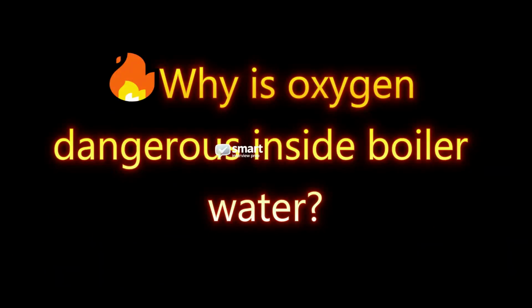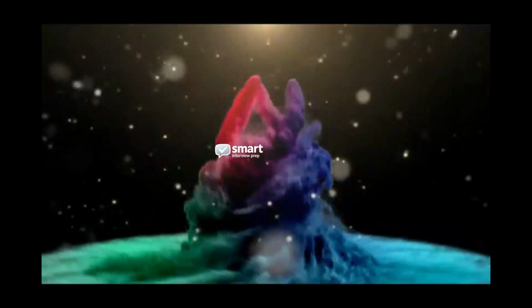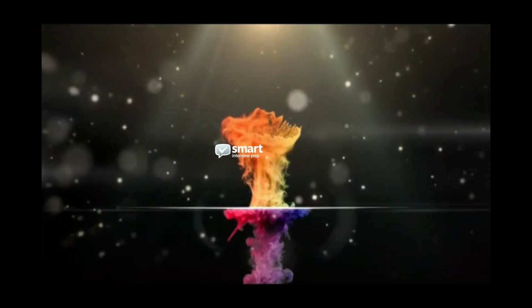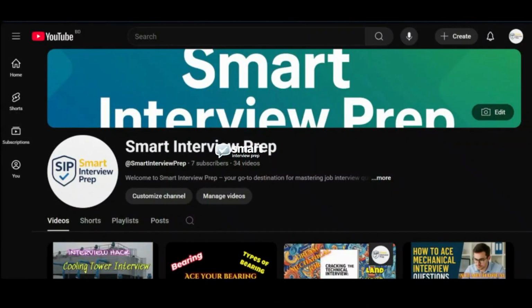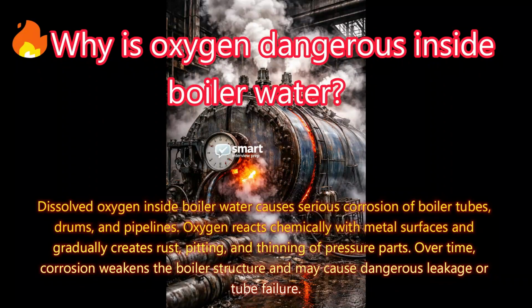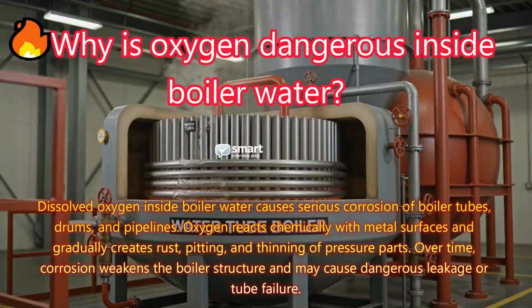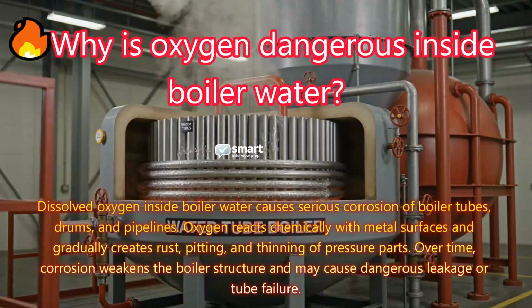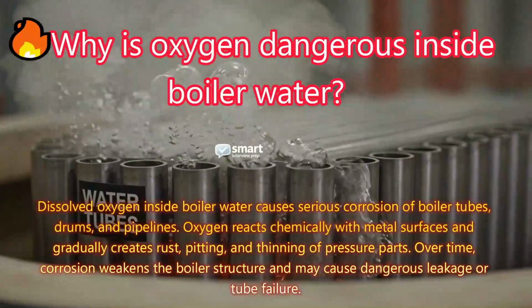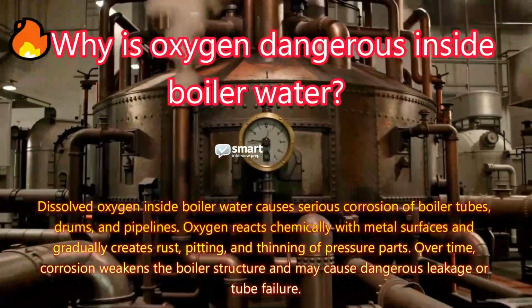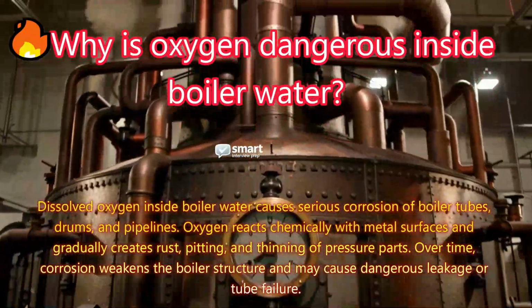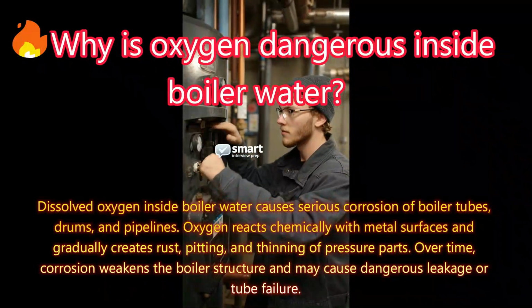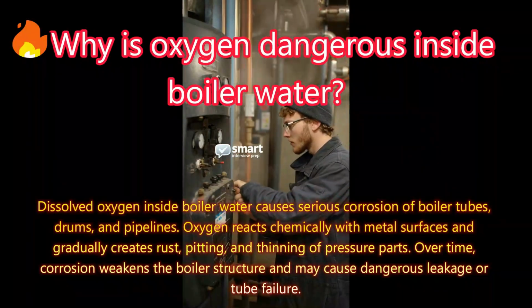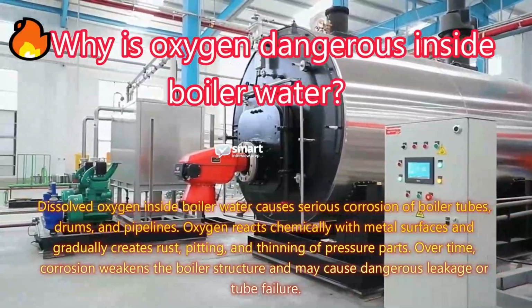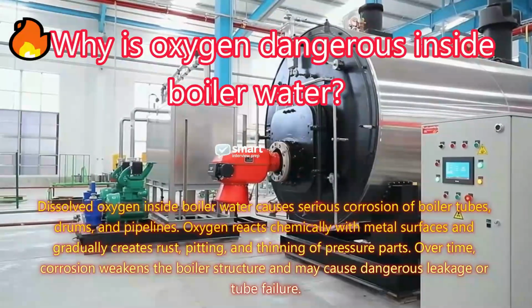Why is oxygen dangerous inside boiler water? Answer: dissolved oxygen inside boiler water causes serious corrosion of boiler tubes, drums, and pipelines. Oxygen reacts chemically with metal surfaces and gradually creates rust, pitting, and thinning of pressure parts. Over time, corrosion weakens the boiler structure and may cause dangerous leakage or tube failure.